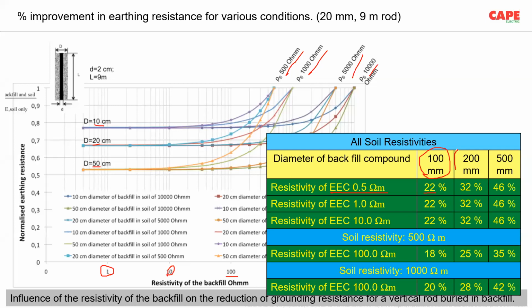Now, if you fill 200 millimeter, then the improvement is 32%. If you fill 500 millimeter, that means almost half a meter all around the earth electrode, you get about 46% improvement. So basically, the area all around the electrode where we put the earth enhancing compound is a serious factor influencing the final resistance. Now, here you see the resistivity of the earth enhancing compound at 0.5 ohm meter, 1 ohm meter, and 10 ohm meter. Again, the resistivity of the earth enhancing compound doesn't matter.